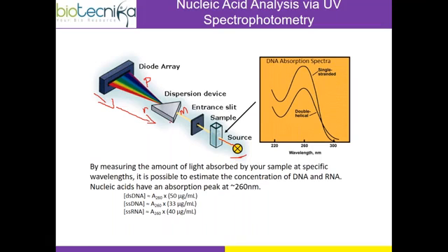But if you see, most of you will get a digital number 0.1, 0.2, 0.3. But the same spectrophotometer can be used for spectral analysis. I think when you guys do research, you will know. So in the same spectrophotometer, I can choose whether I want a spectral mode or I want an absolute number mode. So whatever you see in the colleges and whatever your number, even the protein estimation, whatever you see 0.01, 0.2, 0.5, all those things are absolute number endpoint. But you can choose a spectral analysis also.